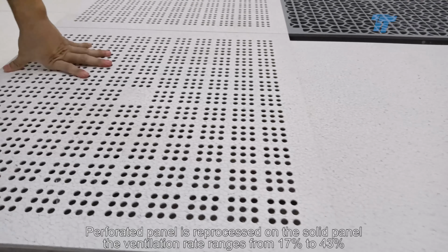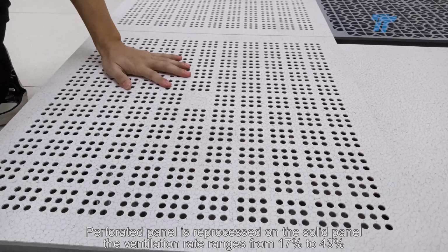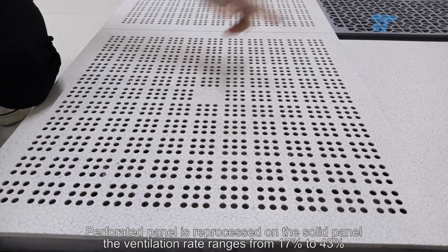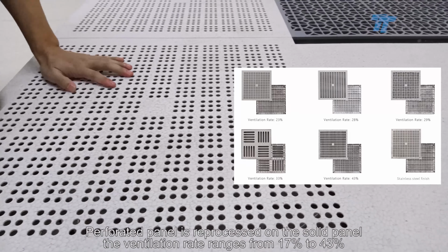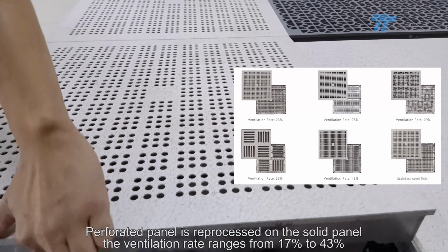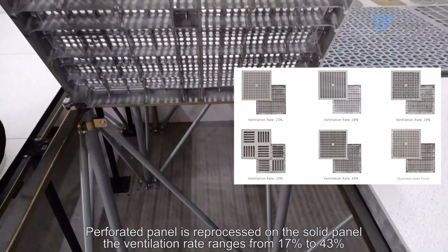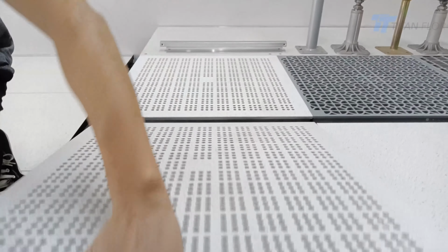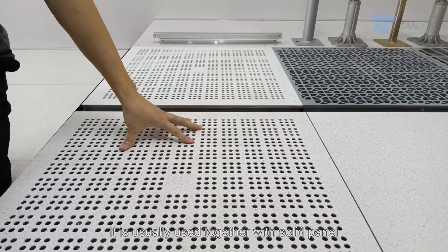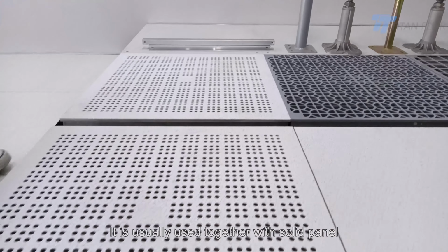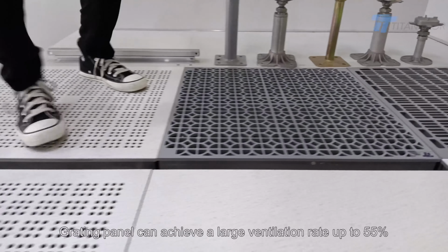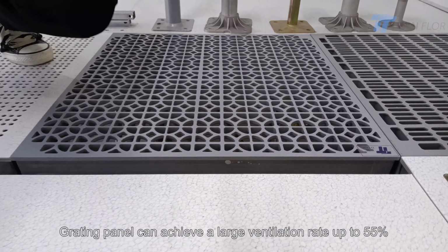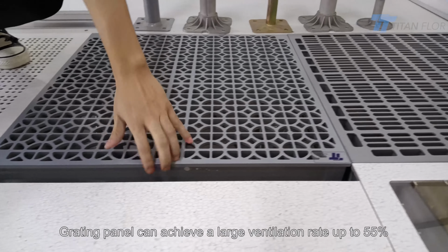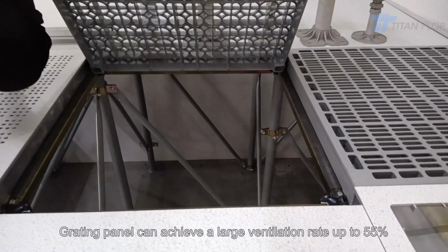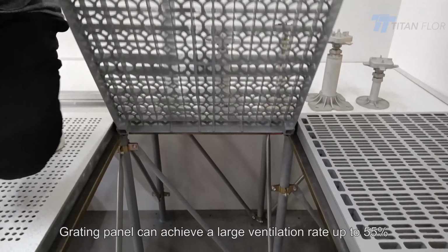This one is perforated panel. Perforated panel is reprocessed on the solid panel. The ventilation rate ranges from 17% to 43%. It is usually used together with solid panel. This one is grating panel. Grating panel can achieve a large ventilation rate up to 55%.